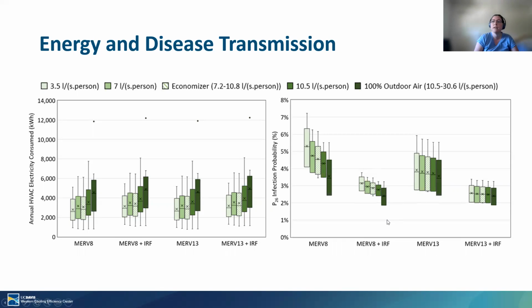But what we can see here is that this is increasing ventilation rate. As we increase ventilation rate, you can see that the infection probability drops as we would expect. But then if we go to a MERV 13 filter that's filtering a higher percentage of those particles, increasing ventilation doesn't do as much, because every time we recirculate that air through that filter, we pull out a lot of those particles. And then if we add in-room filtration, we tighten that down even more. And I should mention the amount of in-room filtration from portable air cleaners that I've modeled here is pretty substantial. This would be like 2 sort of large portable air cleaning units, I think around 600 CFM for that classroom.